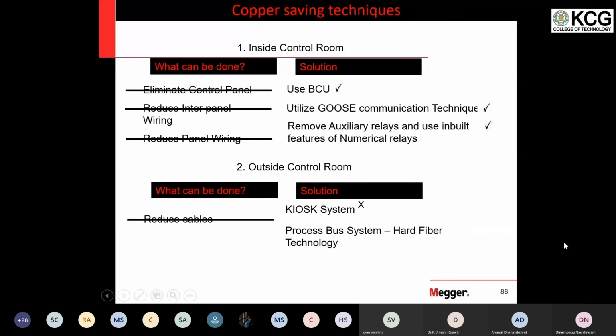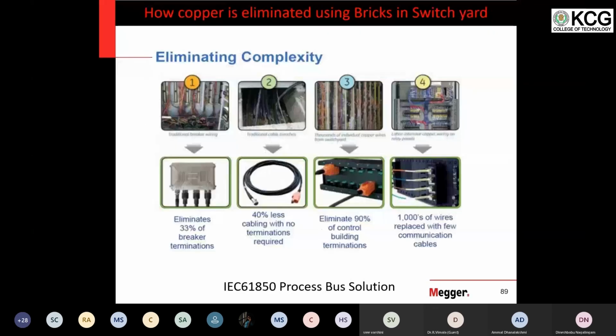Now, what is a process bus technology? It's very simple. Whatever disadvantage that we saw in kiosk has to be eliminated. Whatever advantages that we saw in kiosk, that has to be still there. So when we have a combination of these two, then we have the process bus technology. So let's see that. Here we call this a merging unit. What you see here is a merging unit. So the architecture is going to be simple like this.